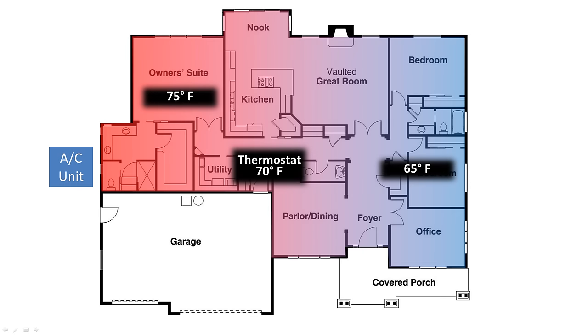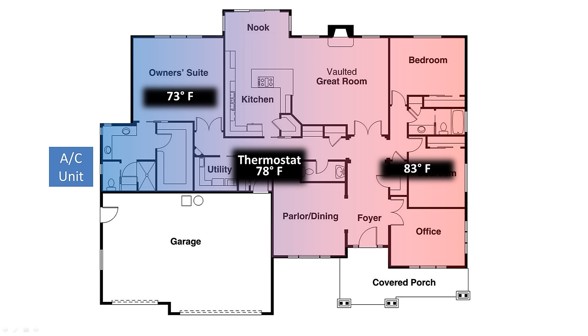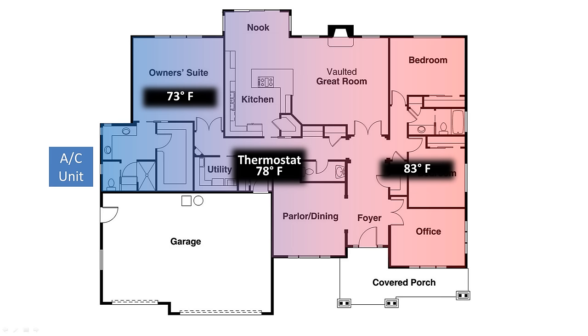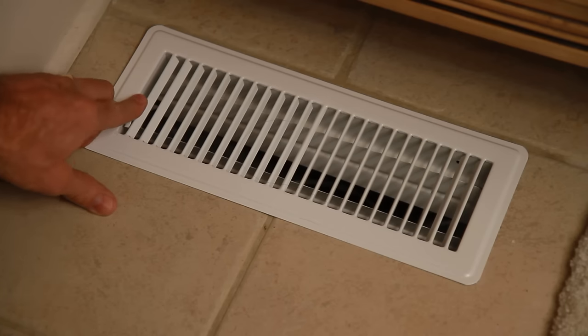Here's what I saw in my house. In the winter, I'd set my thermostat to 70 degrees, and the side of the house closest to the AC unit was about 75 degrees, while the opposite side of the house was 65 degrees. In the summer it was reversed — I'd set my thermostat to 78, and right by the AC unit those rooms would be 73 degrees, while the opposite end of the house would be 83.